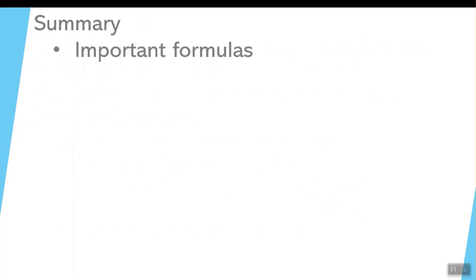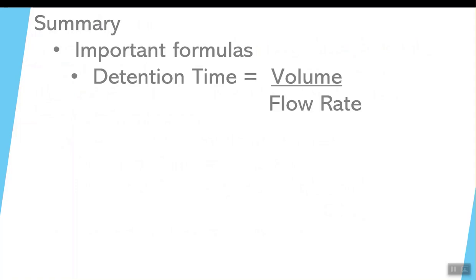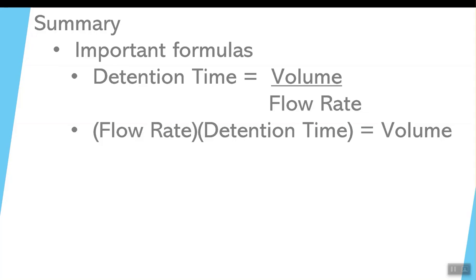Summary. When we're looking at these, the important formulas for this section is detention time equals volume over flow rate. Now if you flip that around, then flow rate, bring it to the other side of the equal sign. Instead of dividing, it now becomes multiplying. Flow rate times detention time equals volume.